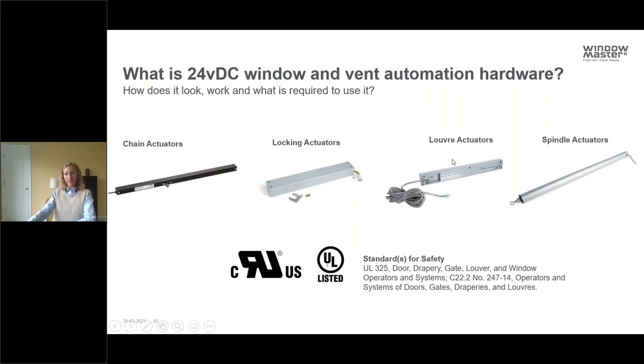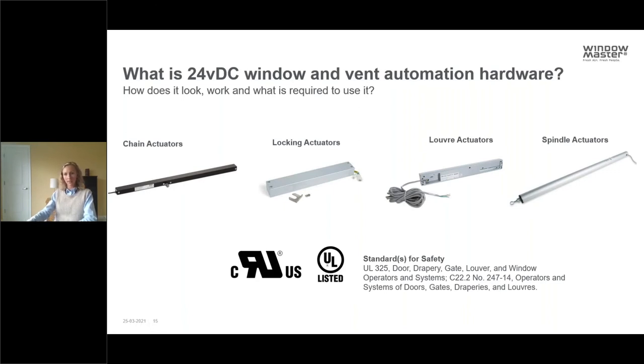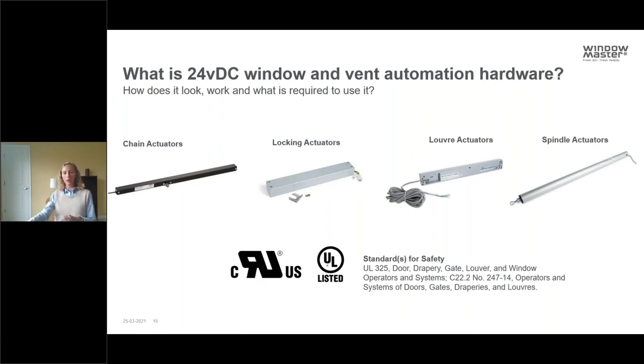We also have louver actuators and spindle actuators. Spindle actuators are strong but do protrude into the space — great for very heavy windows, especially skylights where there's snow or ice load. Most chain actuators are UL 325 certified. Some locking actuators and spindle actuators are not, but we'll guide you through that for your specific project. Most of the time in North America we use chain actuators because they are UL certified.